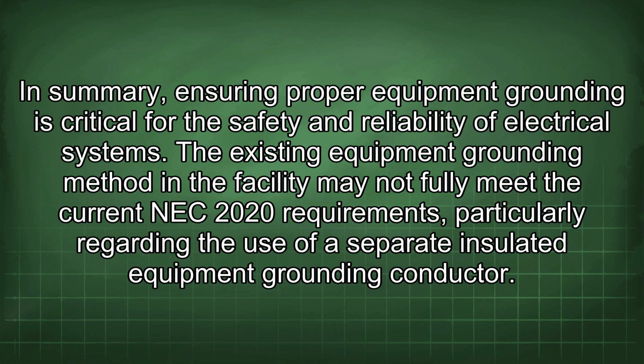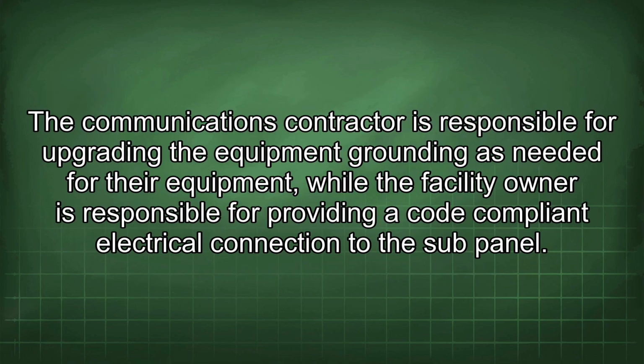In summary, ensuring proper equipment grounding is critical for the safety and reliability of electrical systems. The existing equipment grounding method in the facility may not fully meet the current NEC 2020 requirements, particularly regarding the use of a separate insulated equipment grounding conductor. The communications contractor is responsible for upgrading the equipment grounding as needed for their equipment, while the facility owner is responsible for providing a code-compliant electrical connection to the sub-panel.